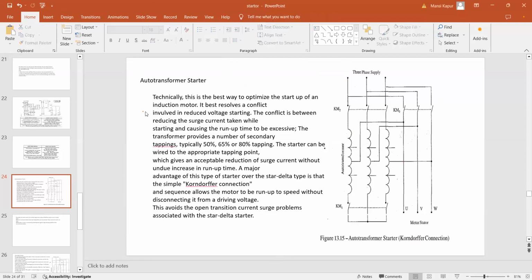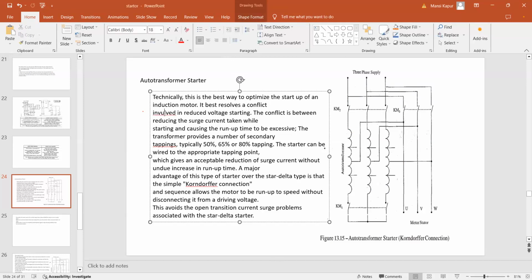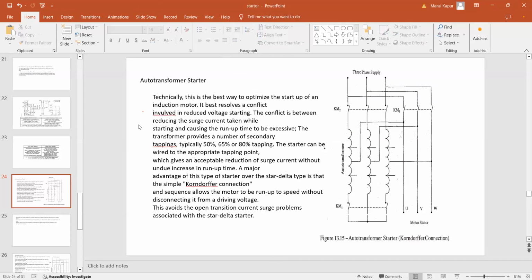Technically, this is the best way to optimize the startup of an induction motor. So this is the best method. It best resolves the conflict involved in reduced voltage starting. The conflict is between reducing the starting surge current while starting and causing the run-up time to be excessive. The transformer provides a number of secondary tappings, typically 50%, 65%, 80%. The starter can be wired to the appropriate tapping. So you can take the wire for your starter from any position in the winding, right?